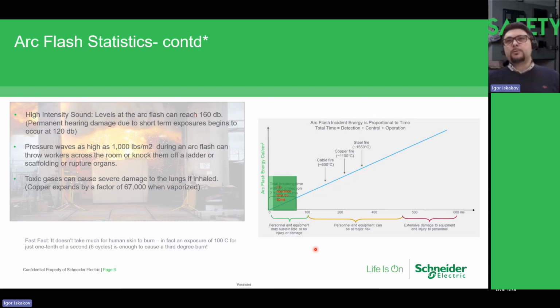So this is a huge amount of time, and usually to reduce it, of course, the first step is modernization of the circuit breakers and regular maintenance, which helps to secure this time. But one of the most important is the operation time of the system which detects the arc flash in less than 10 milliseconds and sends the command to open the circuit breaker. And this is one of the important points, and this is the difference between the protection relay and arc flash protection.